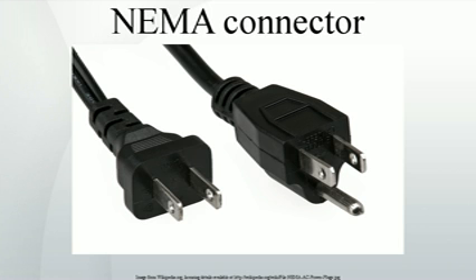NEMA 10. NEMA 10 devices are a curious throwback to an earlier time. They are classified as 125/250V non-grounding, hot neutral, yet they are usually used in a manner that effectively grounds the appliance, though not in a manner consistent with most modern practice. As commonly used, 10-30 and 10-50 plugs have the frame of the appliance grounded through the neutral blade. This was a legal grounding method under the National Electrical Code for electric ranges and electric clothes dryers from the 1947 to the 1996 edition.